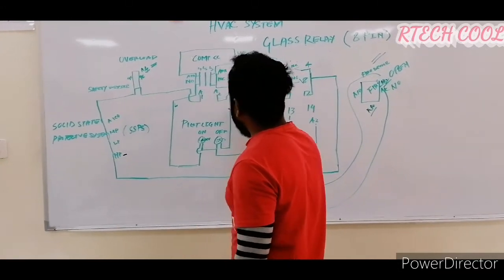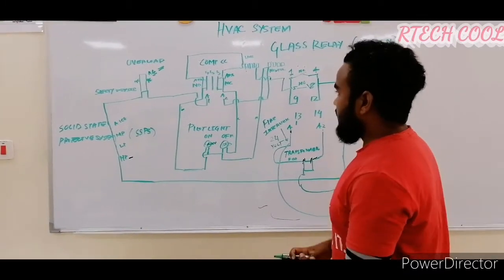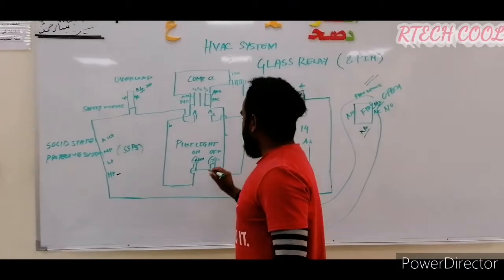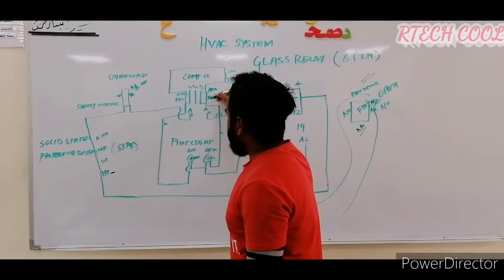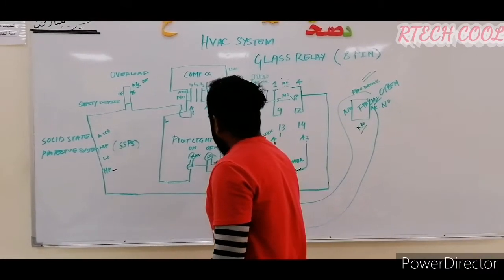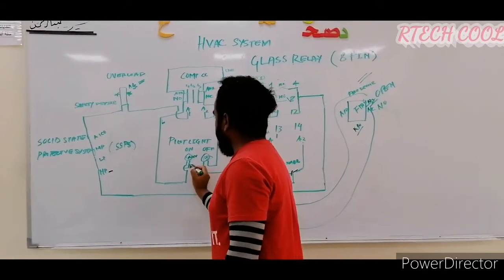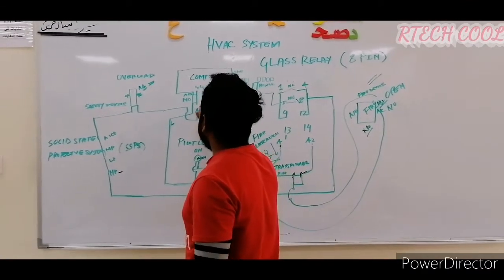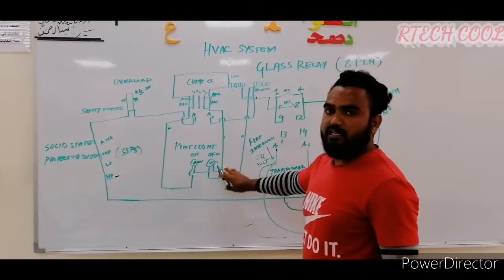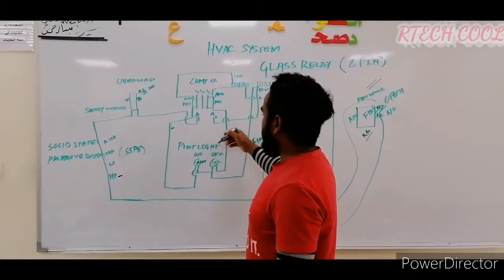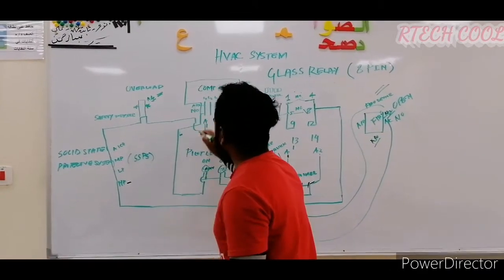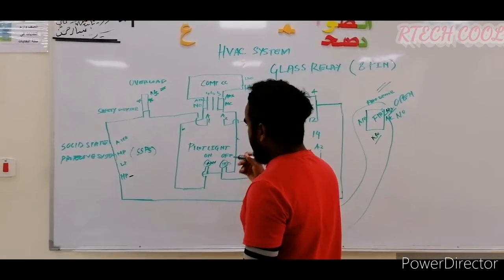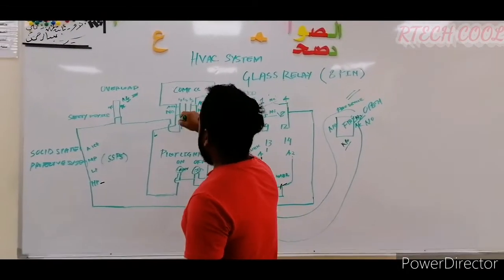From the NO we get one signal, and from the NC we get another — these go to the pilot lights in the control panel. In the control panel, we always see an on/off light showing compressor status. There is a red light and a green light. When the compressor starts and the contactor energizes, the NC opens — so the red light turns off — meaning the compressor is running. The NO closes, so the green light indicates the compressor is running. You can go to the control panel room or the AHU room and see the green light on means the compressor is running.